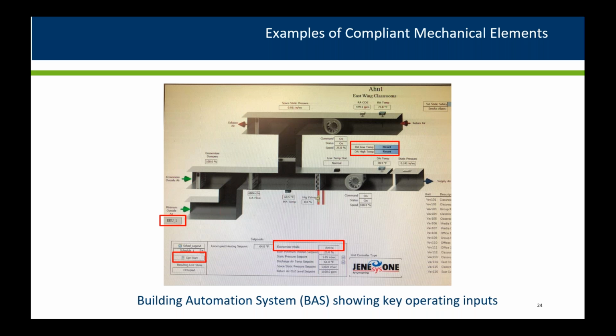In general, facilities with a building automation system make it easier for code officials to verify operating conditions. However, if the facility does not have a BAS, it is much harder for on-site verification. That puts emphasis on plan documentation, which is in general very important, but even more so for mechanical code elements when a BAS is not in the design.